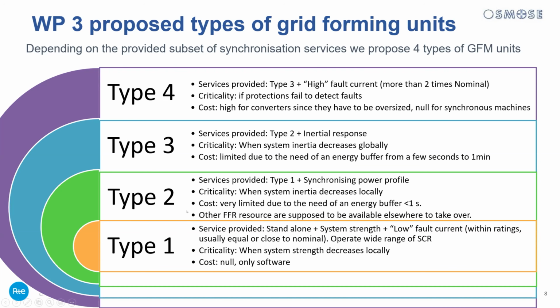Then type 2 is type 1 plus what we call synchronizing power profile, which means when you have an angle shift, you need to provide a peak of power for a very short amount of time. It's necessary when you have inertia that decreases locally. For example, if we keep rotating machines in Central Europe, but in Spain you just have photovoltaics and wind, you don't have an inertia issue at European level, but you would still have an issue in Spain if you don't have this kind of grid forming. It has very limited cost because it's a very small amount of energy needed.